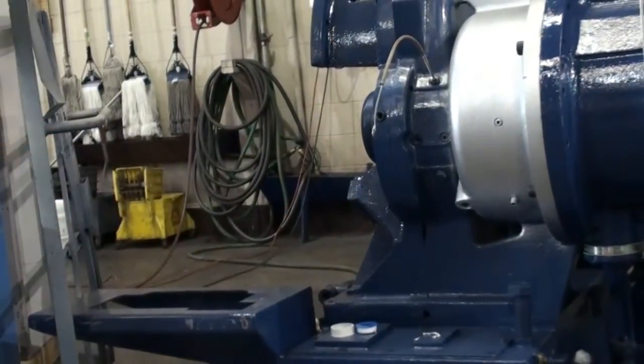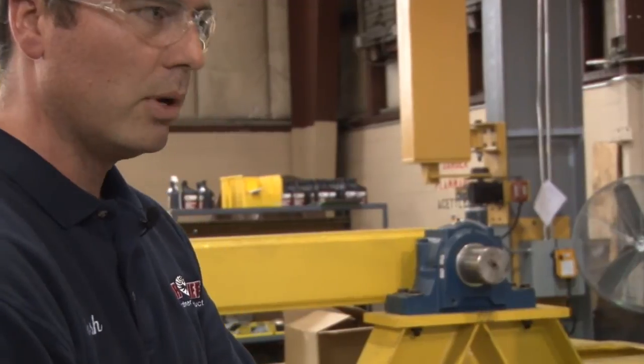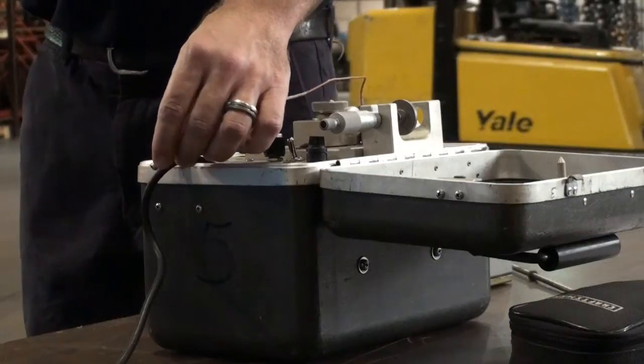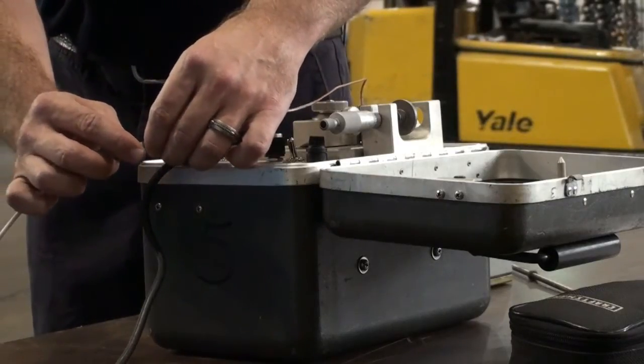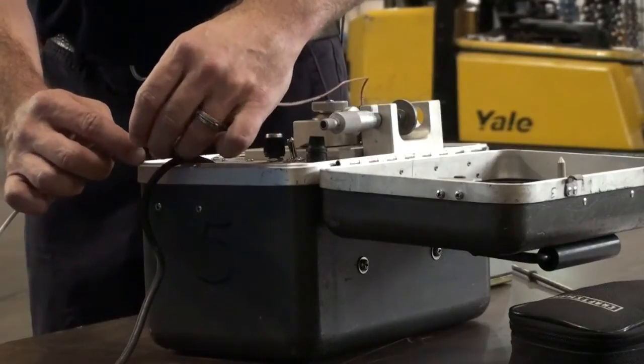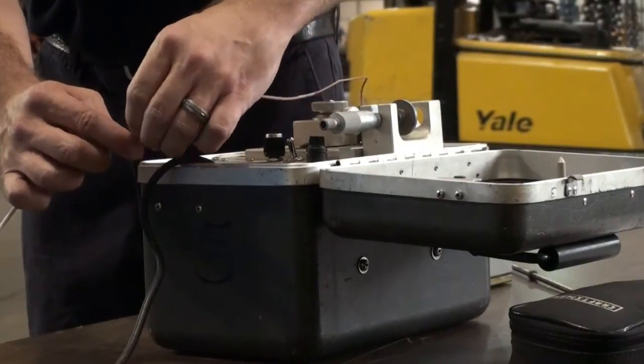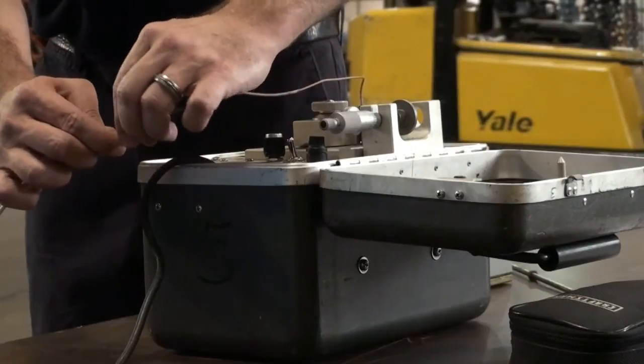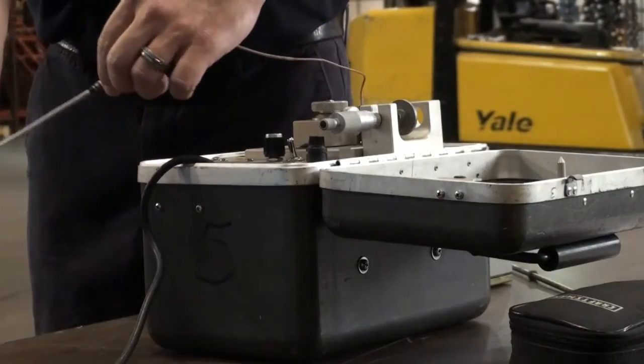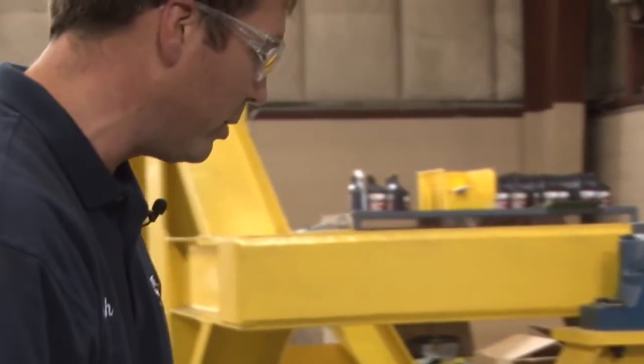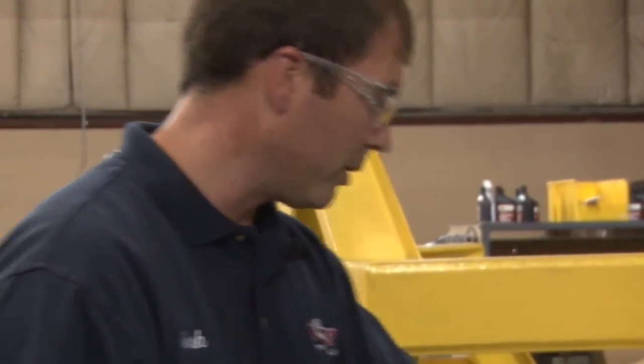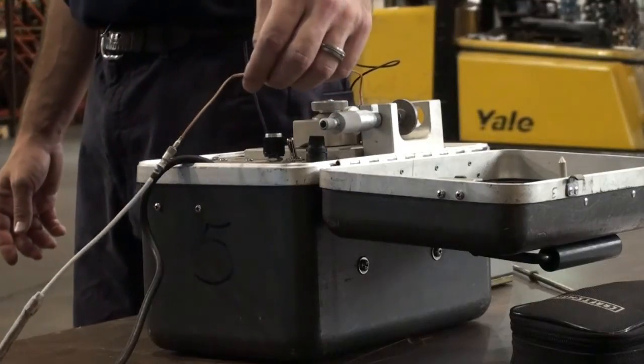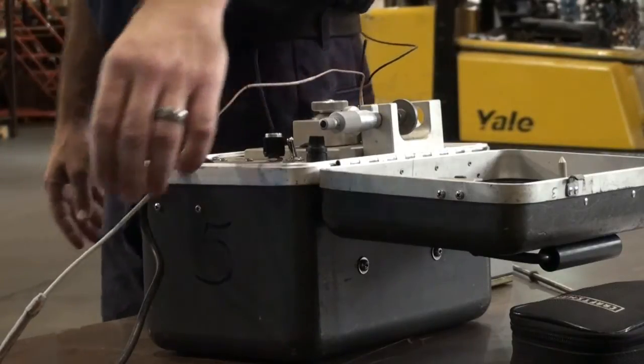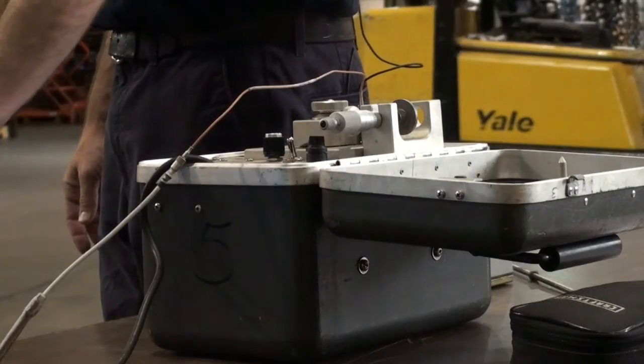We're going to disconnect the probe cable from the probe itself. We're going to bring it over here to the TK3. This is a Bentley Nevada brand. There are other equipment available that are as equivalent as this machine here, but the main focus is to simulate vibration through a different probe than what's in the machine, the cable, the transmitter inside the panel, and the panel itself. We want to make sure all these components are working properly.